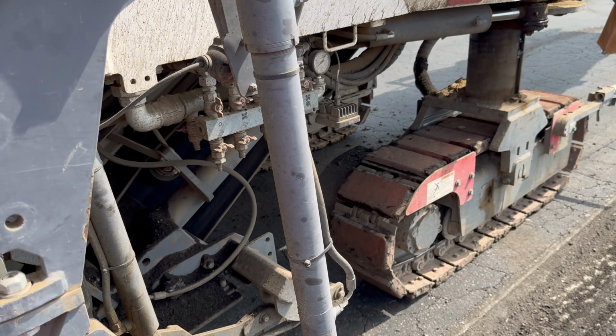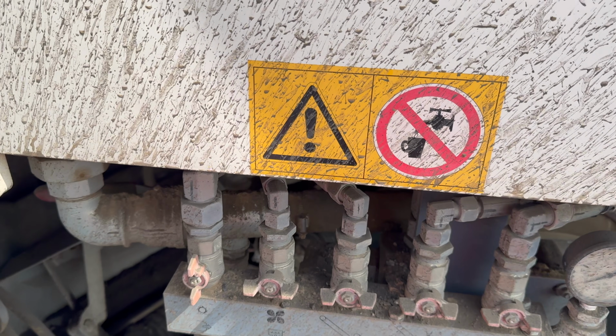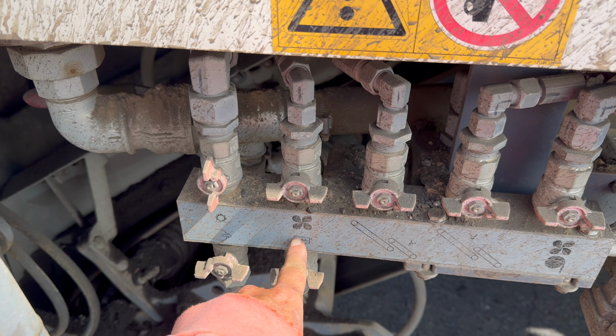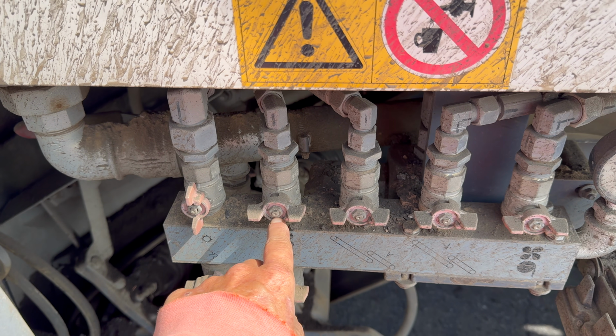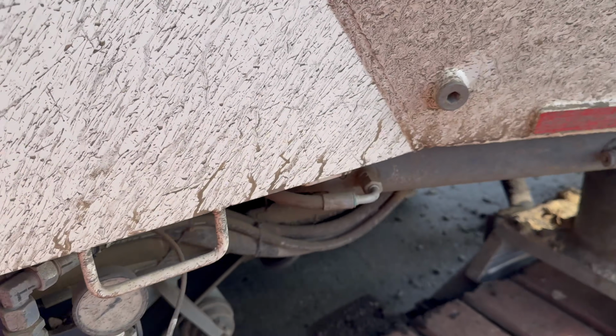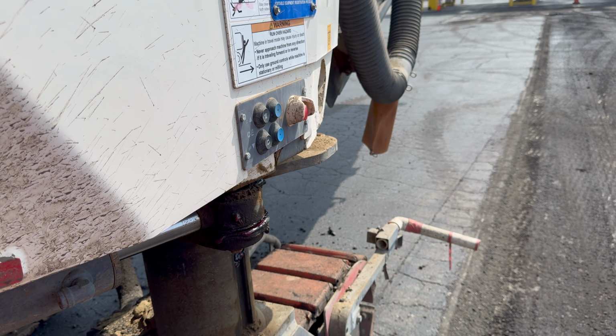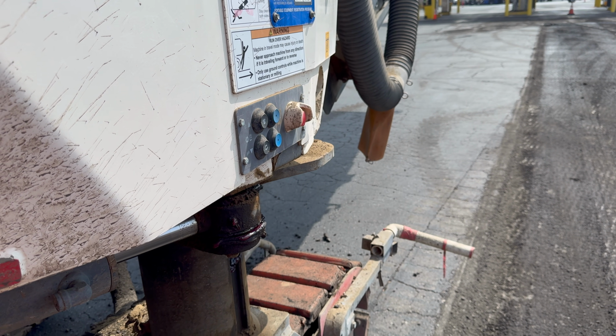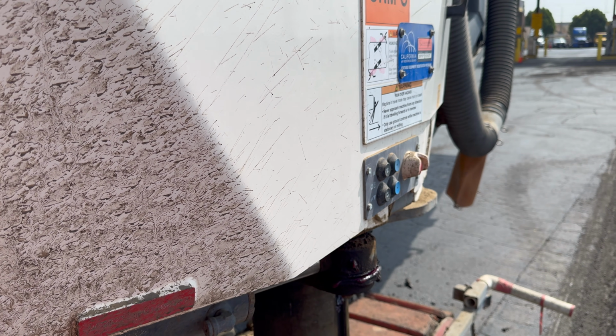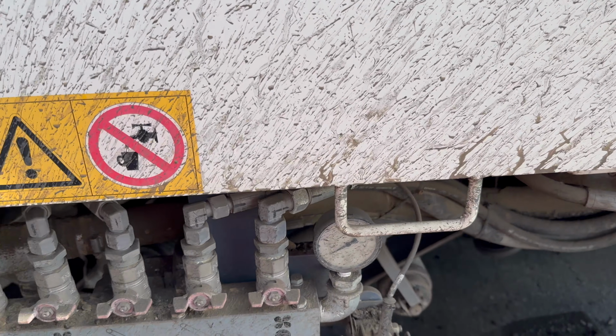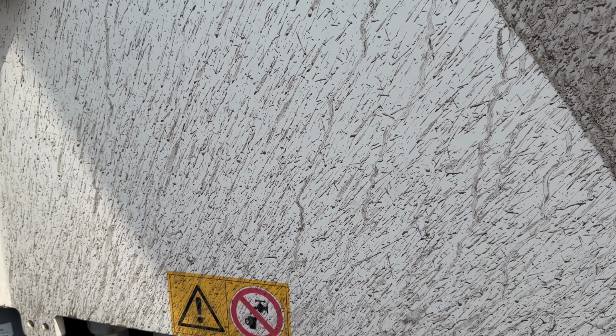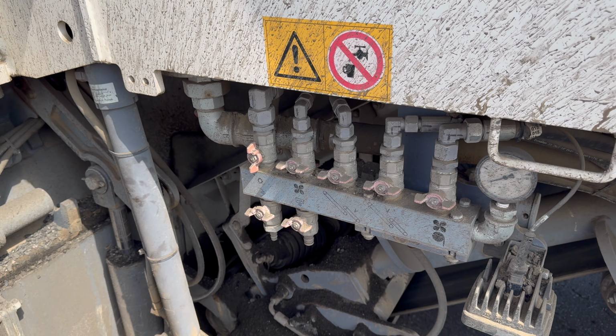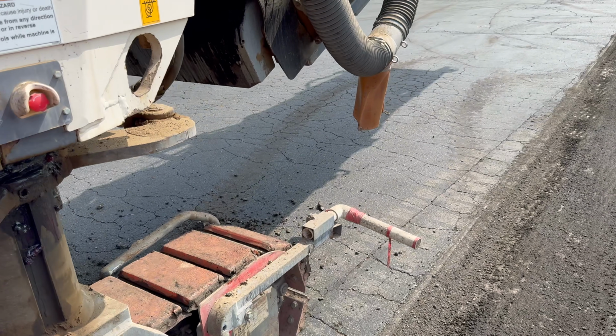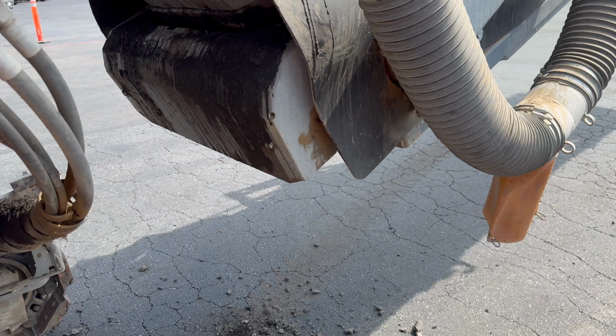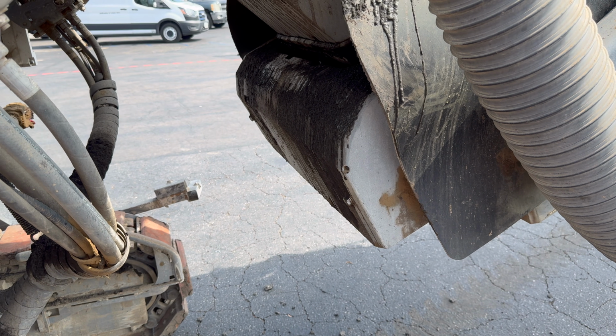The other one I recommend, on the spray system, this one's clogged up, so it needs to get unclogged. But this one here for the fan, leave that just barely cracked on, to the point that when you raise the machine up out of the ground and your fan shuts off, you get a little bit of water dribbling out of those yellow duckbill things up there. That'll keep the dust and dirt from making it up to the fan, and it'll help keep it clean a little longer, because this chimney is inside the machine right here. It'll catch all the dust and let it drop out, and all the dirt, and let it drop out, and it'll keep things from plugging up. A lot of guys don't like it because it drips a little water in the front when you shut the fan off, but it's totally worth it. It keeps the machine running a little better, a little longer.